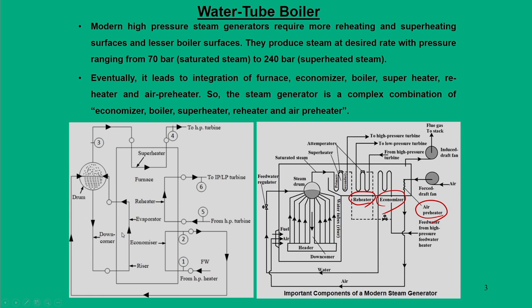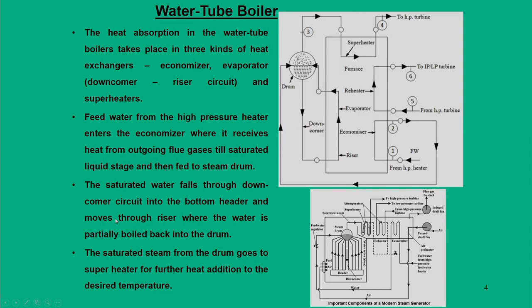All heating requirements are supplied by this steam generating unit. To summarize: feed water from the high pressure heater enters the economizer where it receives heat from the outgoing flue gases until it becomes saturated liquid, then is fed to the steam drum. The saturated liquid falls through the downcomer circuit into the bottom header and moves to the riser where water is partially boiled back to the drum. Finally, saturated steam from the drum goes to the superheater for further heat addition to the desired temperature.